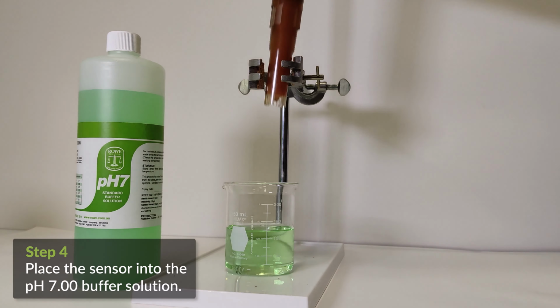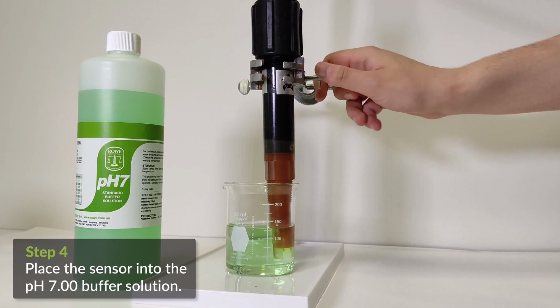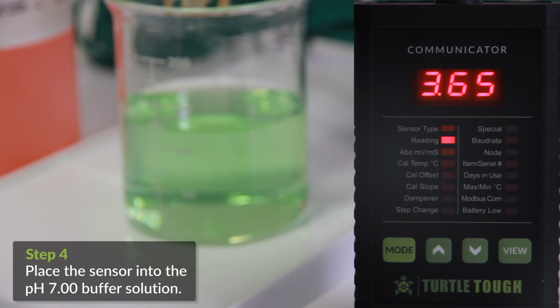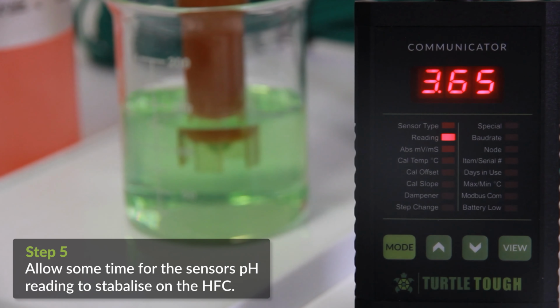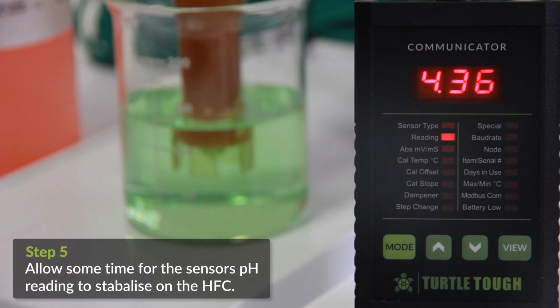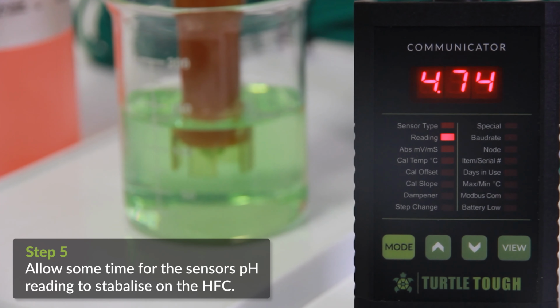Place the sensor into the buffer 7 solution to establish this pH sensor's offset. Allow a few seconds for the reading on the HFC to stabilize. Note that older sensors can take several minutes to stabilize, while new sensors will stabilize very quickly.